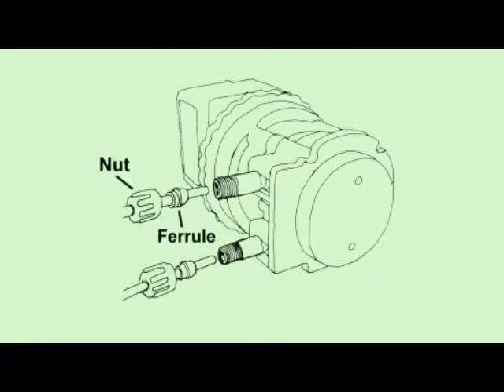The suction and discharge lines are installed to the pump tube fittings with a compression-type seal consisting of the connecting nut and ferrule. The beveled end of the ferrule faces the tube fitting, and the suction and discharge line should bottom into the tube fitting. The connecting nut is secured into the fitting finger tight only and not tightened with pliers or wrapped with thread seal tape.